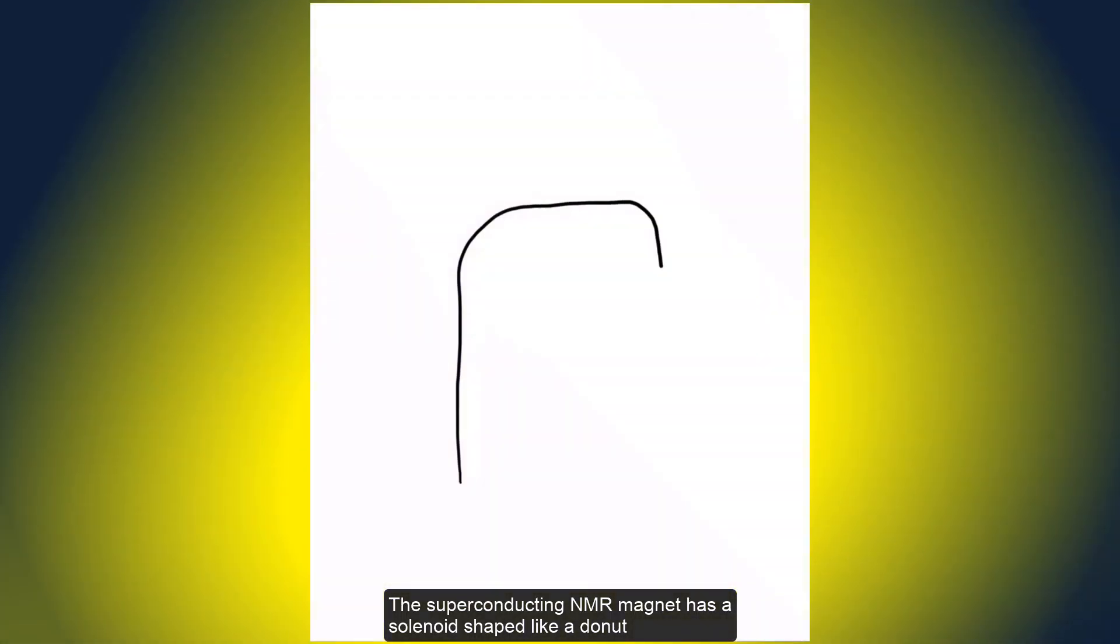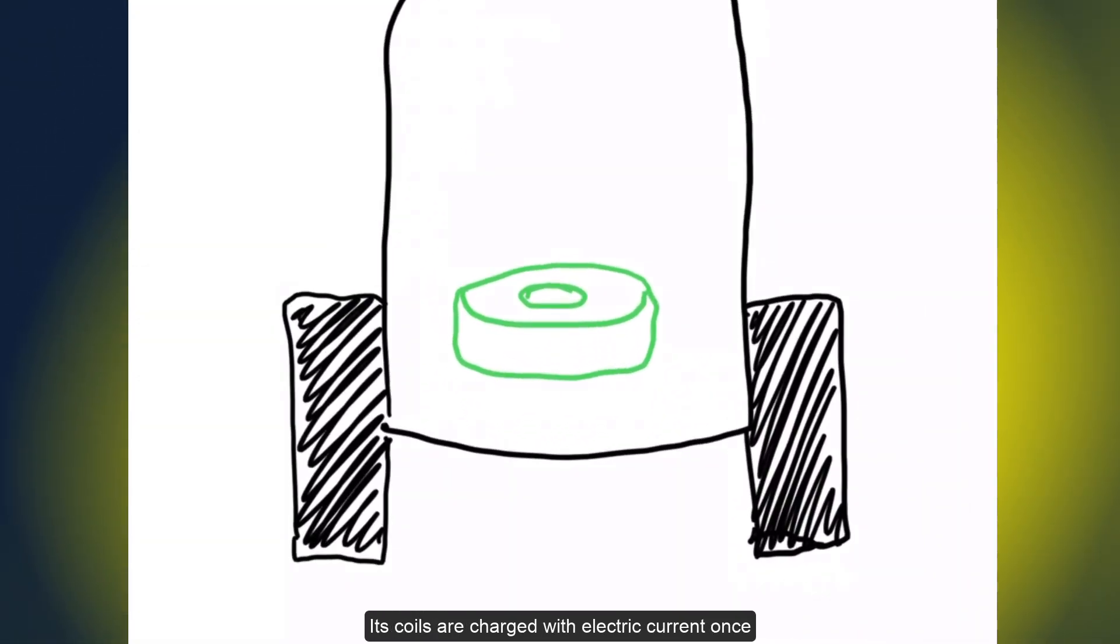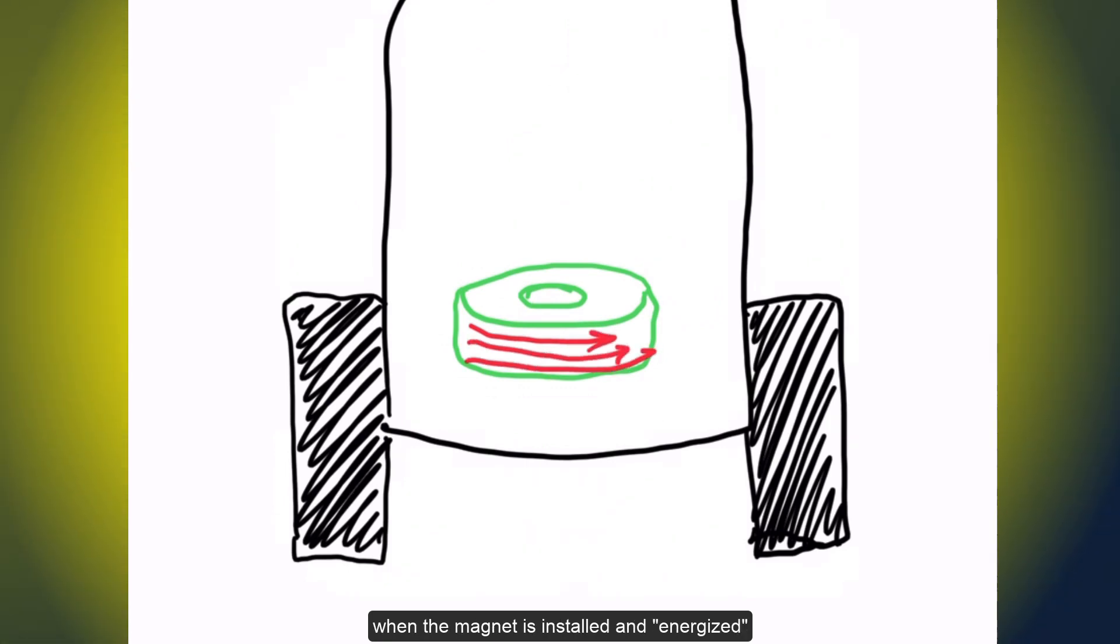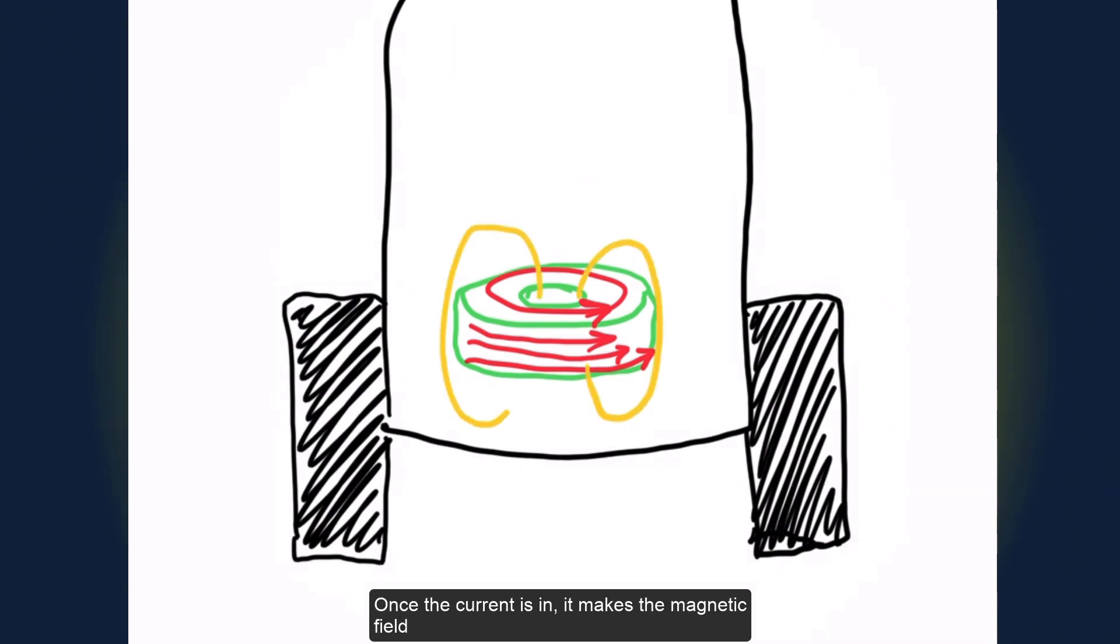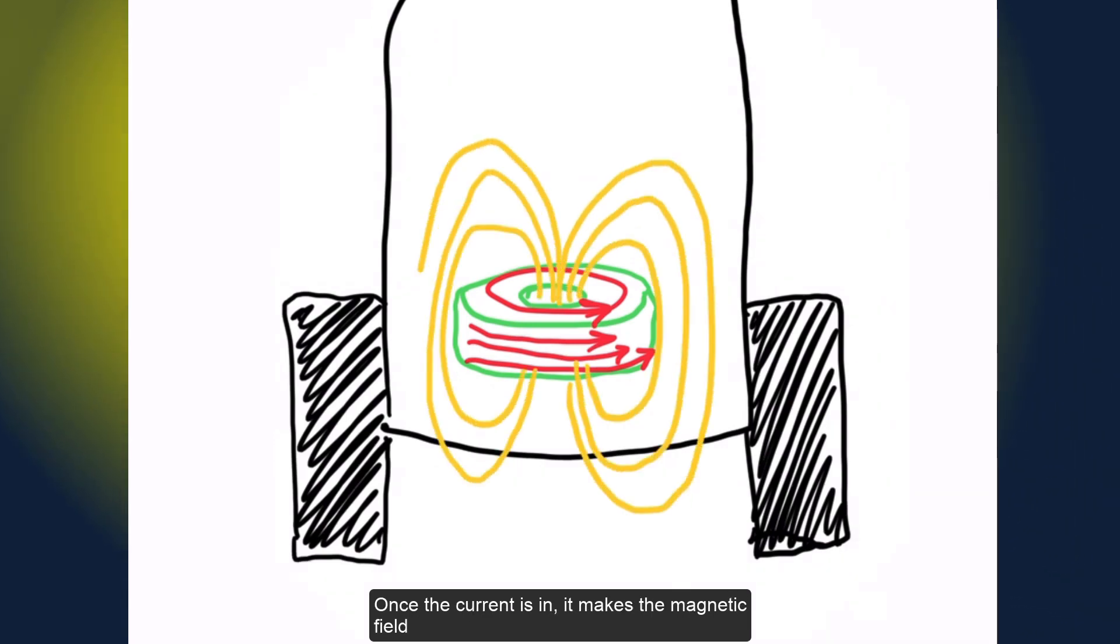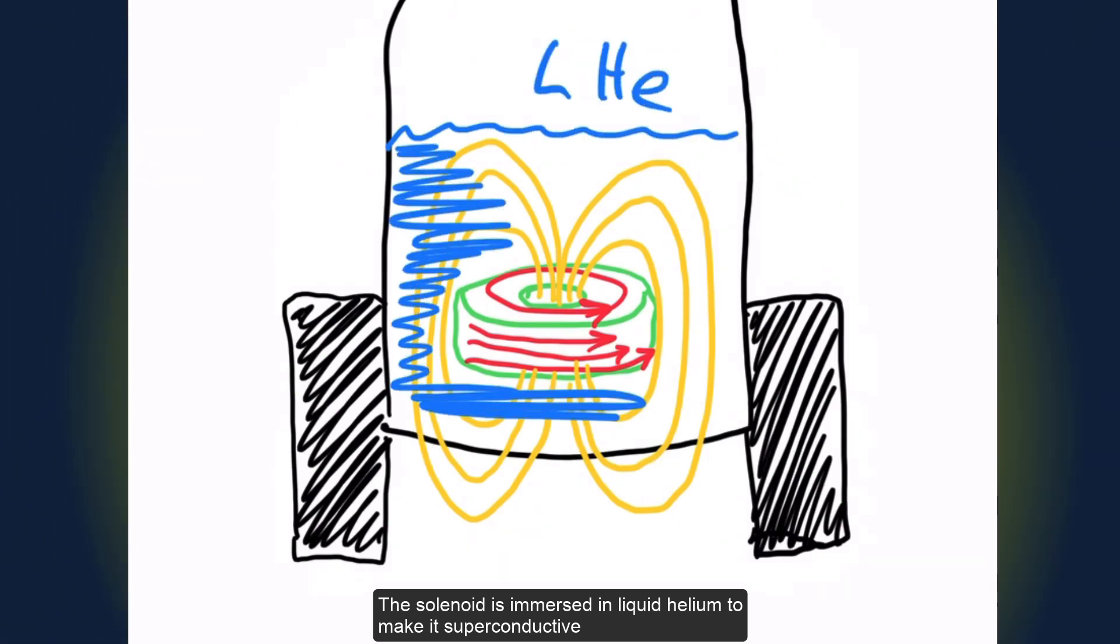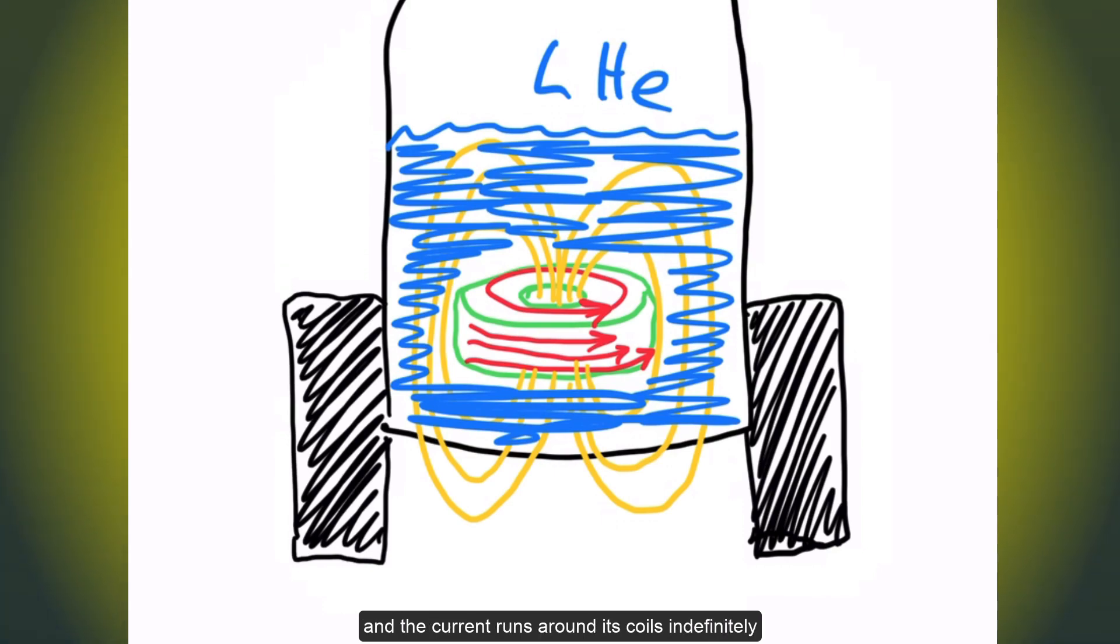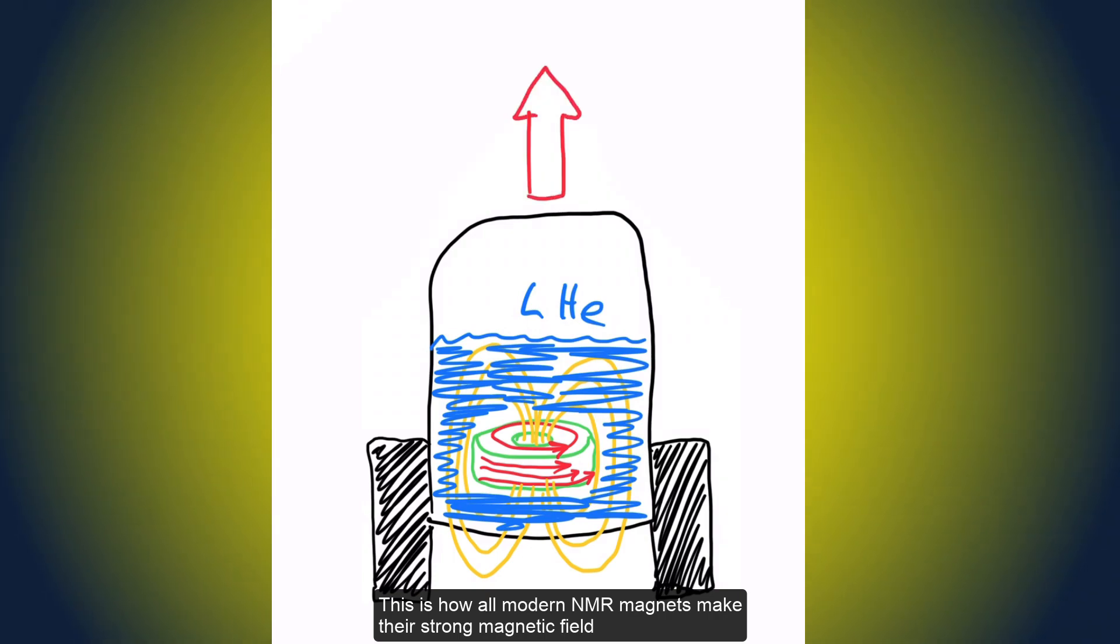The superconducting NMR magnet has a solenoid shaped like a donut. Its coils are charged with electric current once when the magnet is installed and energized. Once the current is in, it makes the magnetic field. The solenoid is immersed in liquid helium to make it superconductive. Therefore, it has no resistance and the current runs around its coils indefinitely. This is how all modern NMR magnets make their strong magnetic field.